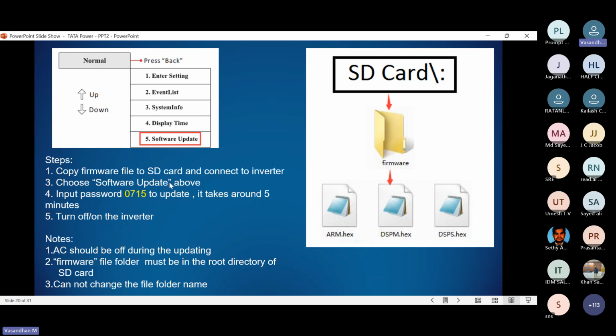They have to arrange a pen drive and laptop. Using an empty pen drive, they have to copy this particular firmware - they should not change any file name, just copy the firmware folder as it is and paste it to the empty pen drive. After inserting the pen drive in the inverter, we choose the software update option, and it will prompt for a password, which is 0715 by default for all inverters.